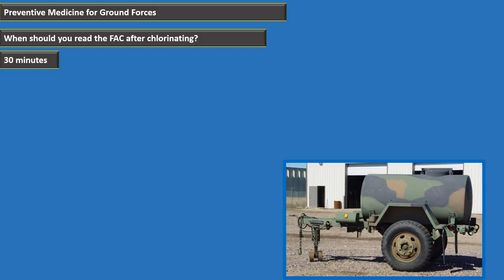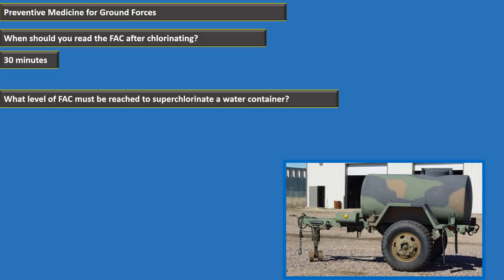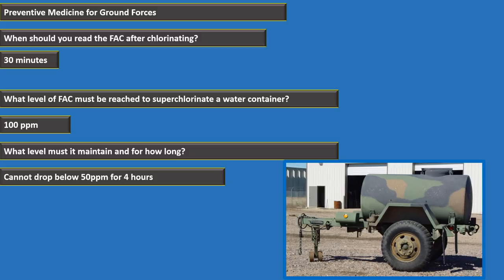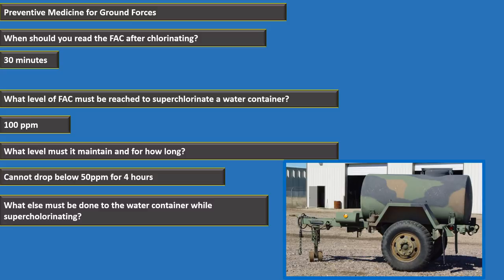To super-chlorinate a water container, the chlorine must reach 100 parts per million, maintain at least 50 parts per million, and be held for at least four hours. During super-chlorination, the word 'POISON — DO NOT DRINK' must be clearly marked on every side of the container and on any water outlets or spigots.